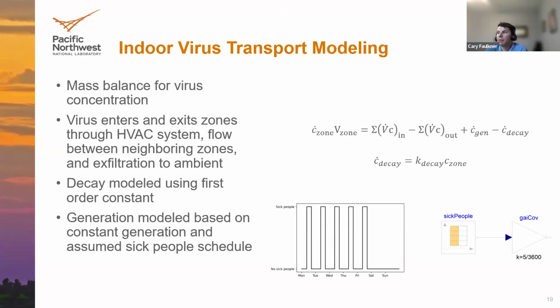And then the generation term, we model assuming a constant generation rate from sick people when they are present in the zones. If you're familiar with Modelica, you can define these tables, which can introduce a schedule to the model. In this case, I showed an example of a typical worker working 9 a.m. to 5 p.m. in this office building Monday through Friday. That can be multiplied by some sort of constant to describe the generation rate, or it could be connected to something else which describes a more variable rate, but this is how we did it, and that 5 divided by 3600 being 5 quanta per hour in this case for our simulations.